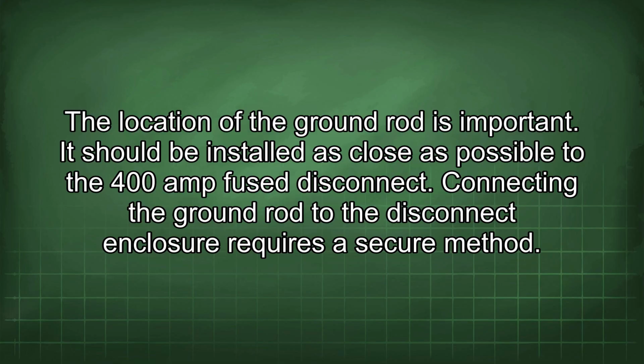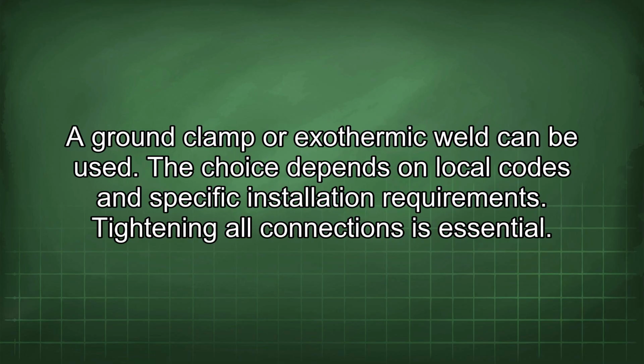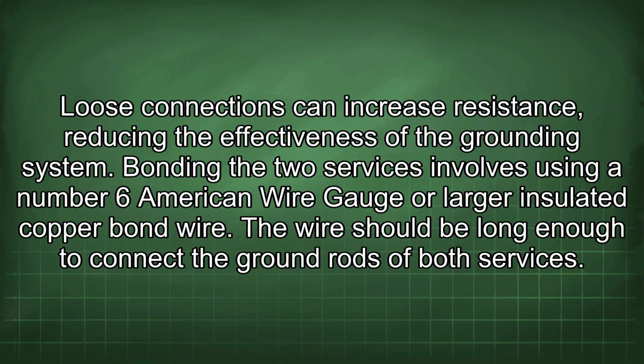Connecting the ground rod to the disconnect enclosure requires a secure method. A ground clamp or exothermic weld can be used. The choice depends on local codes and specific installation requirements. Tightening all connections is essential. Loose connections can increase resistance, reducing the effectiveness of the grounding system.